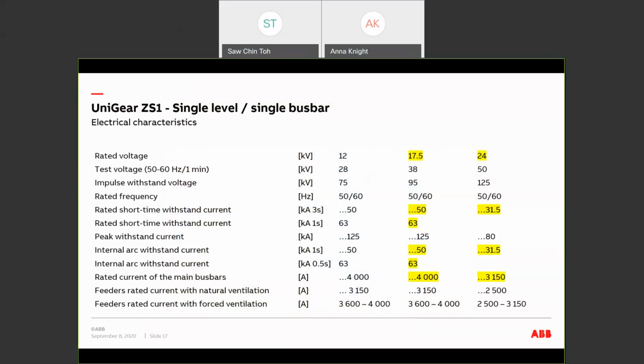The key electrical characteristics of the switchgear are shown in this chart. At 17.5 kV, the maximum fault rating is 50 kA 3 seconds or 63 kA 1 second. The internal arc rating for this switchboard is 50 kA 1 second or 63 kA 0.5 second. The maximum bus bar rating or the panel rating is 4000 amps. At 4000 amps, we'll need to use forced ventilation. For 24 kV, the maximum rating is 31.5 kA at 3150 amps.